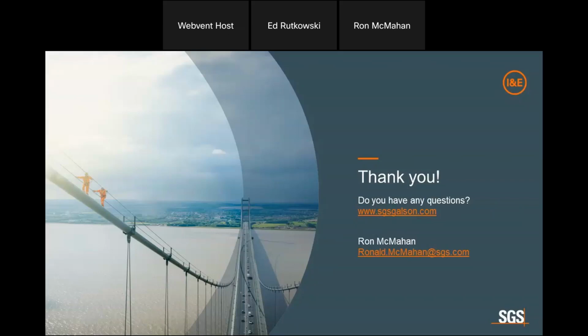So in the proposal for the multi-year contract, we put in annual calibration. We're just completing that round, these 4,500 units, and working with the university in Boston and BPS, we're looking at all this data, and we think 1 year will be sufficient based on the technology that's in the system. It looks solid right now, but it could get to where we maybe do it more frequently. At this point, it looks pretty reliable. The measurements from the previous year had some error, greater than what we've got now on the calibrated system, but not crazy off, not 100%. So if it needs to be increased, we'll work to do that in a time frame better than 1 year.